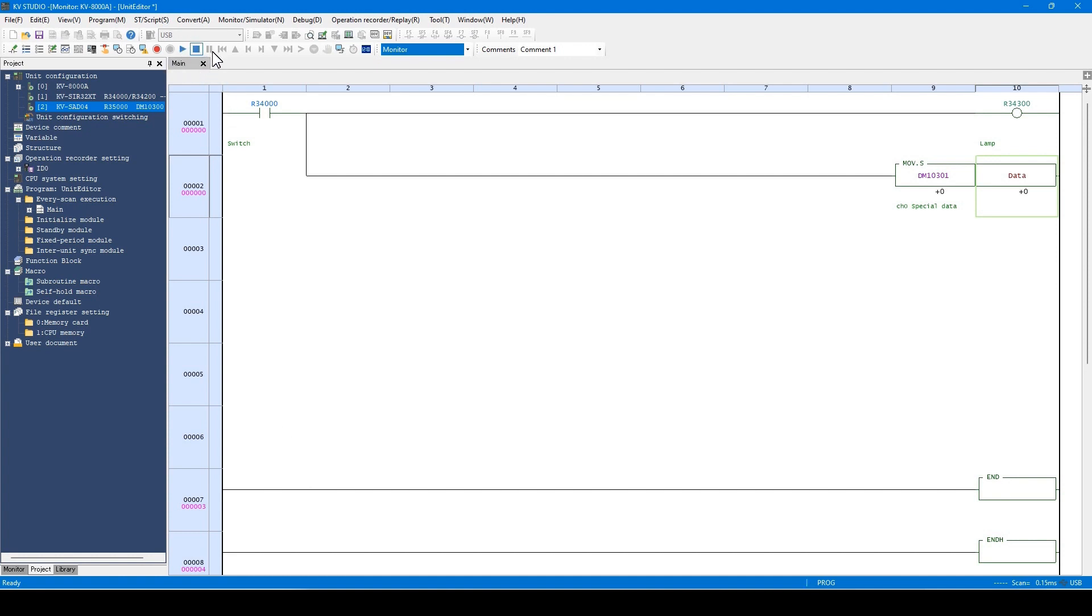As you can see here, because the PLC is in program mode now, no program is running. Even without a program, you can check whether I.O. and analog wiring are correct if the unit setting is transferred.